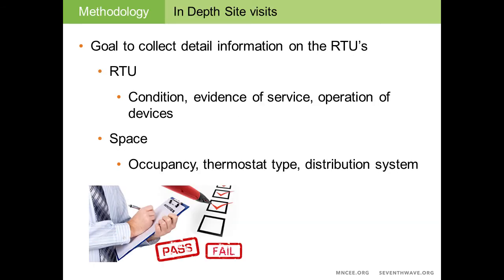So the in-depth site visits, the main goal behind that was to get more detailed information than could be collected from the characterization phase. We wanted to get boots on the ground in these sites and take a look at the condition of the RTU. We wanted to look at the evidence of service, see if there's any operational issues with the devices. And when I say devices, I talk about the fan, the compressors, the sections of the units that are providing service to the space. And in the space, we also wanted to document the occupancy, the thermostat type, and the distribution system that's happening within the site.